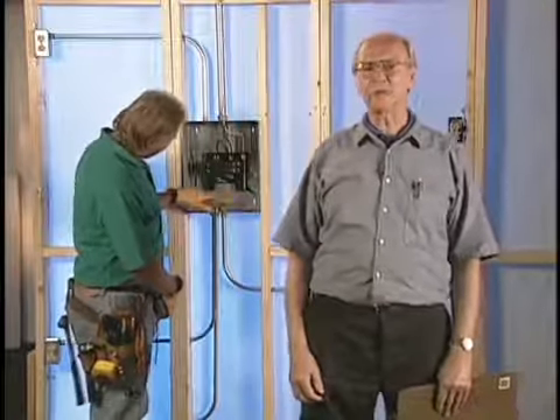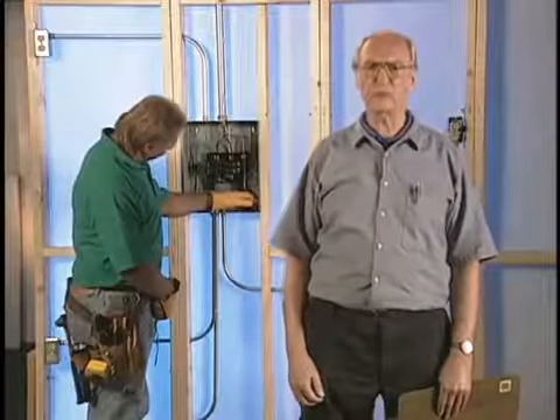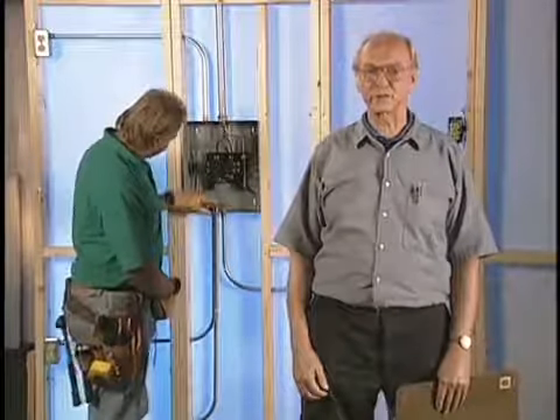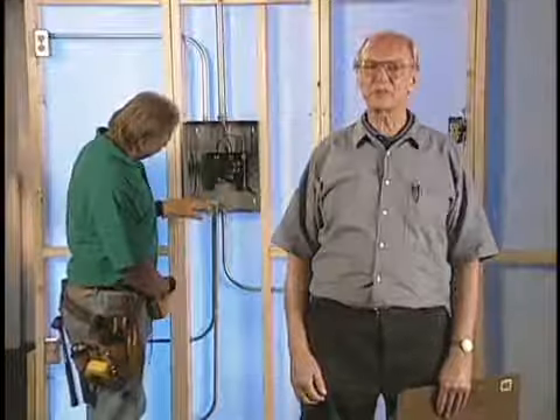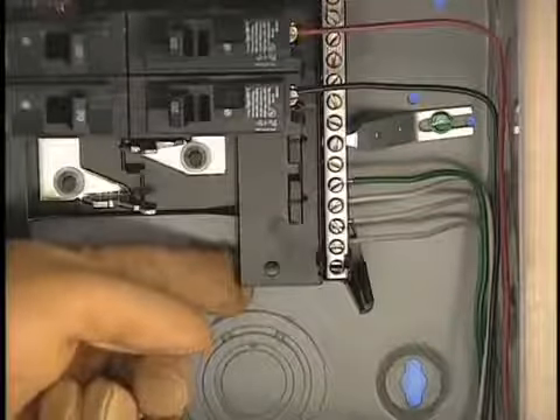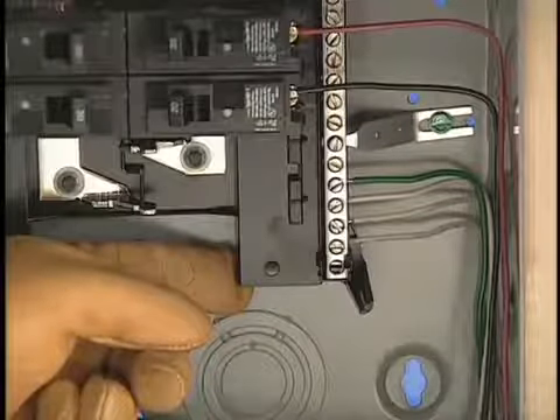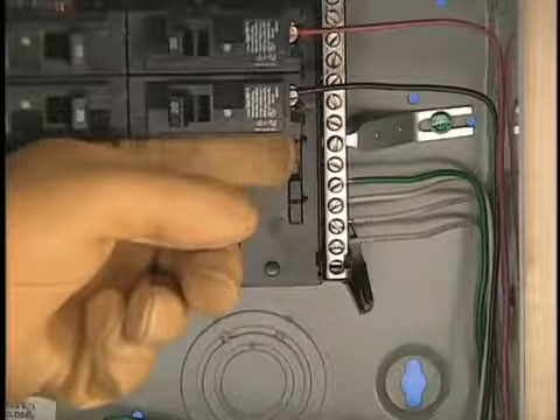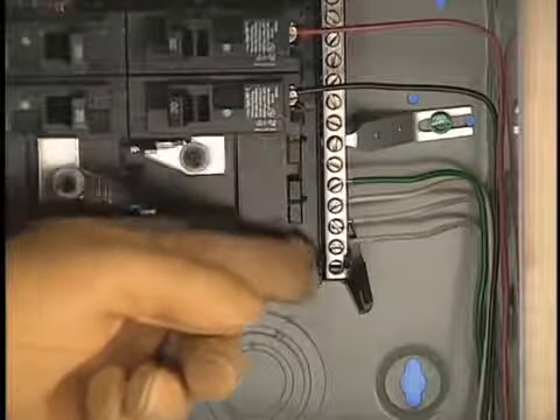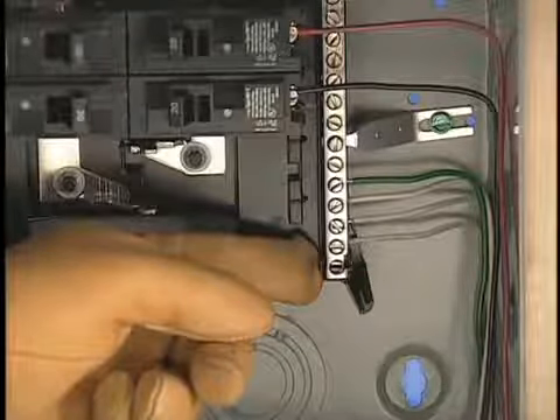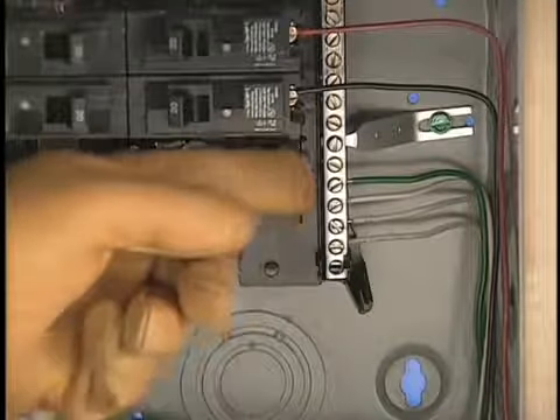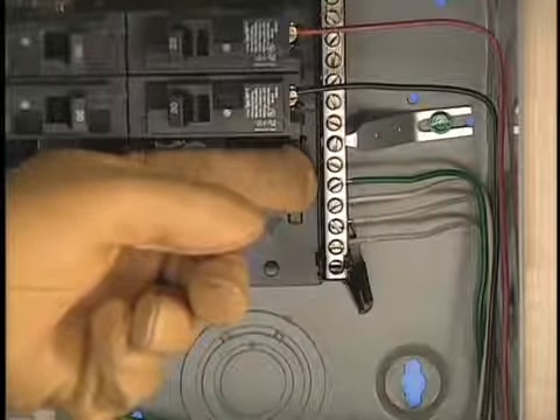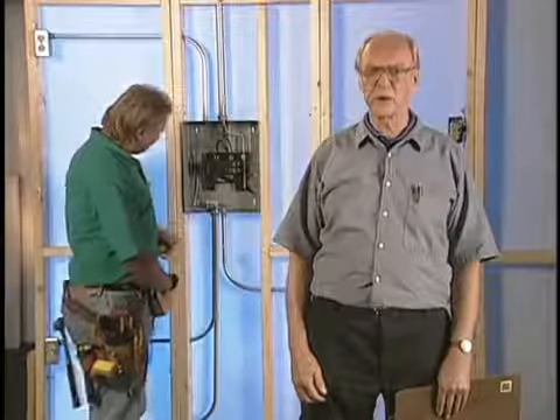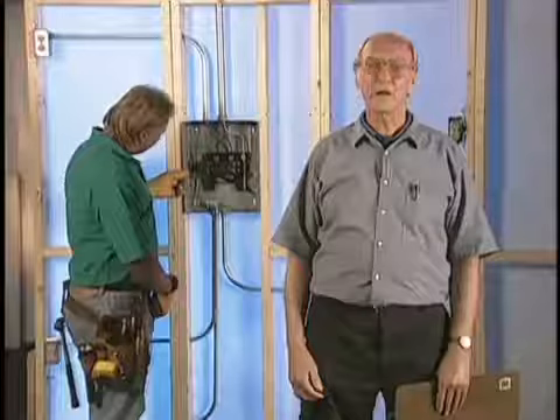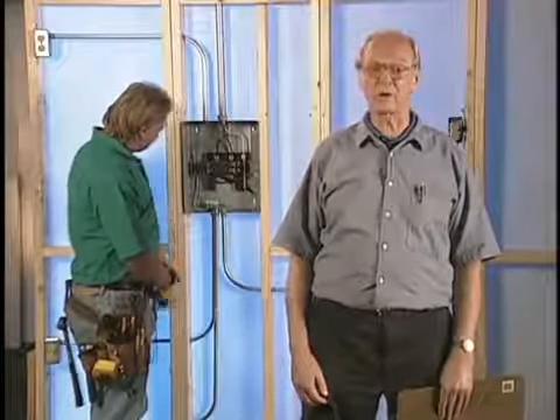After removing the breaker panel cover, perform a visual check. Ask yourself the following questions. Is the neutral bus insulated from the box as it should be? Is there a prohibited bond? Is the bonding screw in or out? It should be out. Are any equipment grounds connected to the neutral bus? They should have their own bus or connectors. Are any neutrals connected to a grounding bus? As you can see, we've put all these errors into this panel.